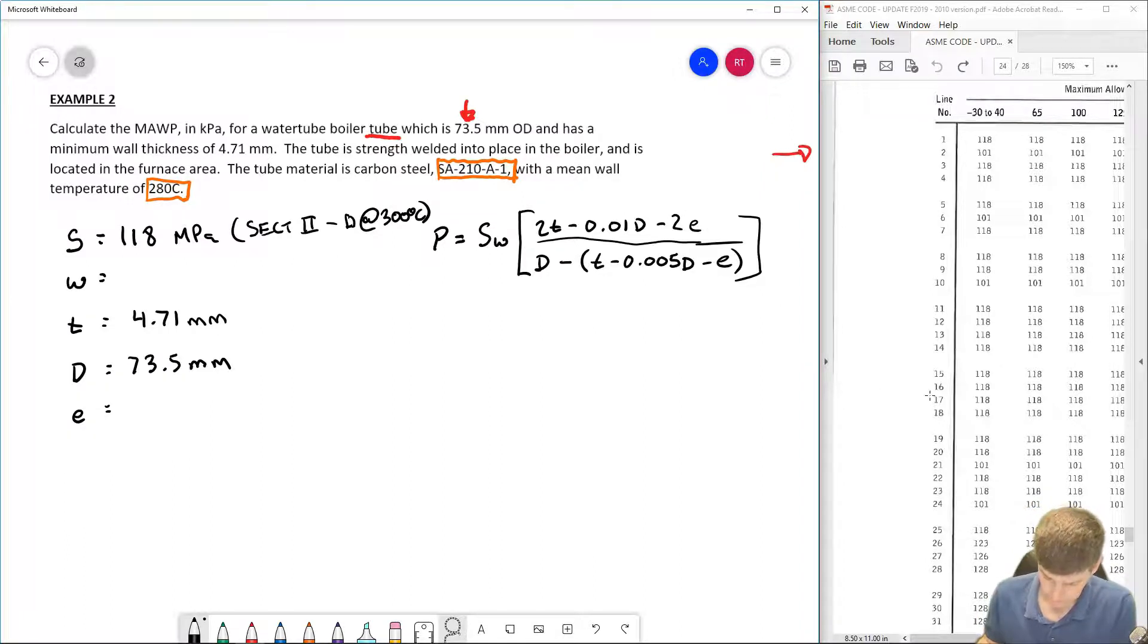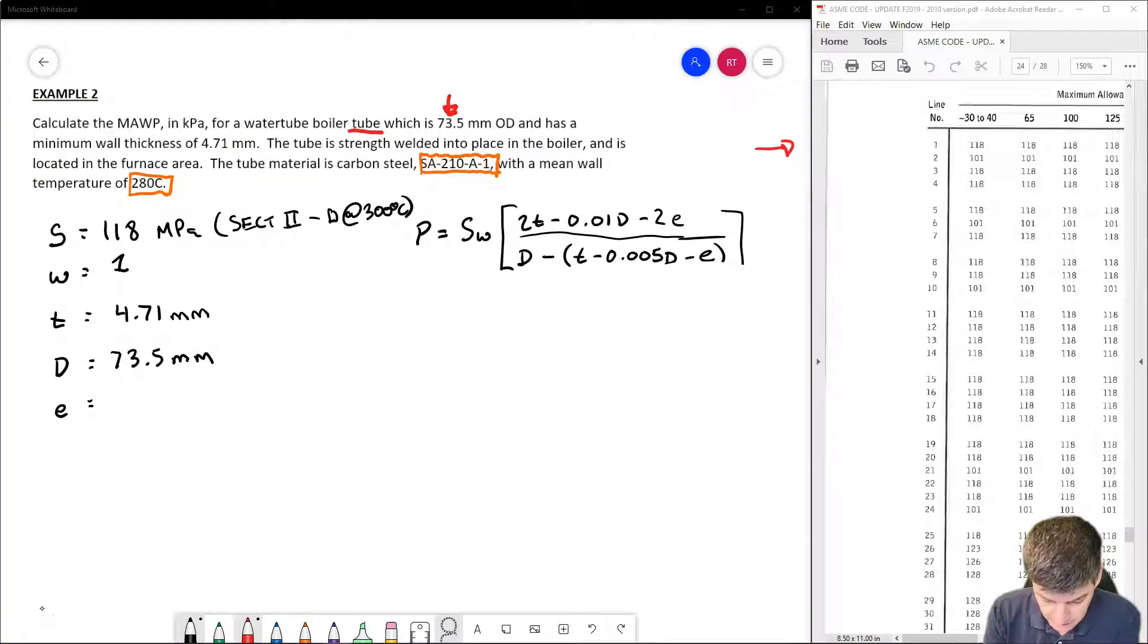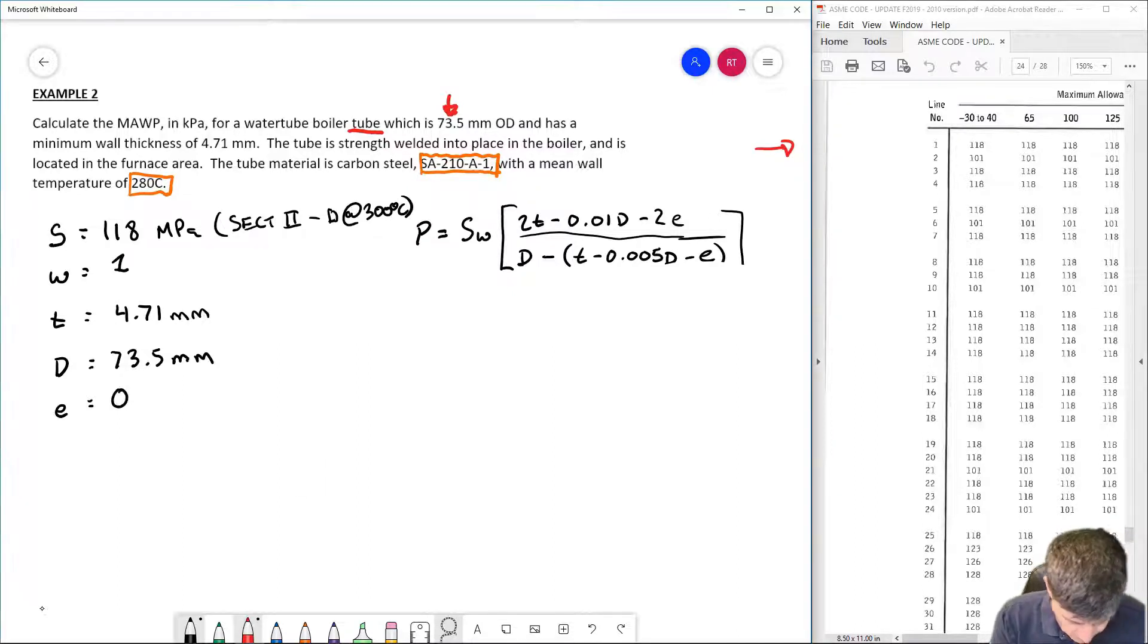Similar situation - we have a low temperature for our mean wall, well below the 500-ish degrees that would be required if we had one of those creep reduction factors. So that meant that W, similar to the last section, is going to be equal to 1. And in addition, because E is a strength welded tube, E is going to be equal to 0.